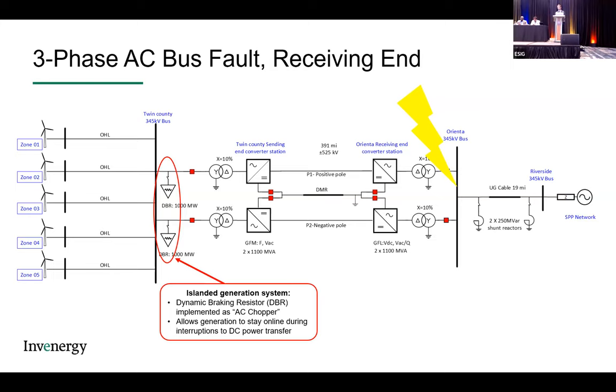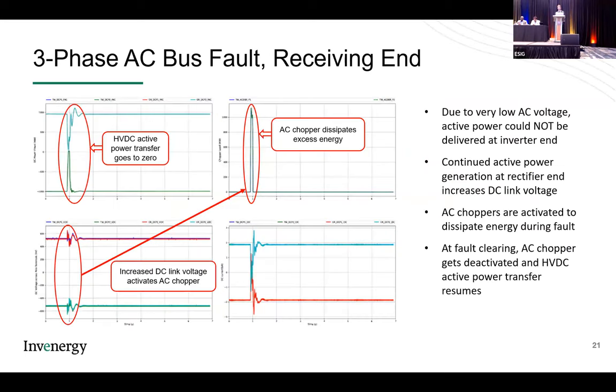So we'll take a really quick look at how that's activated, how it works. And what you see is there's a receiving end bus fault at that inverter terminal. The HVDC active power transfer goes to zero. Then what you see in the bottom there is the DC link voltage starts rising, and the DC link voltage then activates the AC chopper. That's that braking resistor, and that dissipates the excess energy.